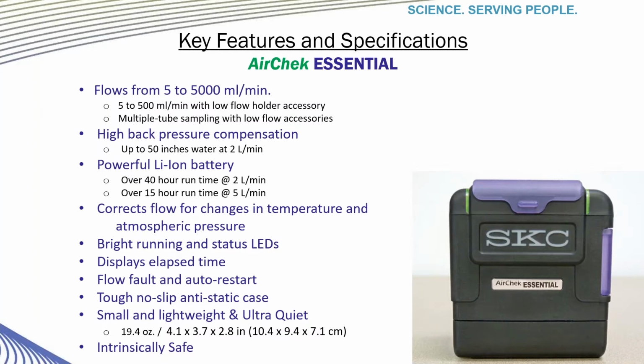The Essential's flow range is 5 cc's to 5 liters per minute. This is a change from some of our past basic pumps like the AirChek 52, which only went up to 3 liters per minute. It will do low flow sampling down to 5 cc's and up to 500 cc's using a low flow holder accessory, something like our all-in-one adjustable tube holder, or just a CPC with a standard tube holder. You can also use the AirChek Essential for multi-tube sampling. It will handle back pressure up to 50 inches of water column at 2 liters per minute and has a runtime of over 40 hours at 2 liters per minute. And even if you have an application where you need to sample at 5 liters per minute, you will still see run times in excess of 15 hours.